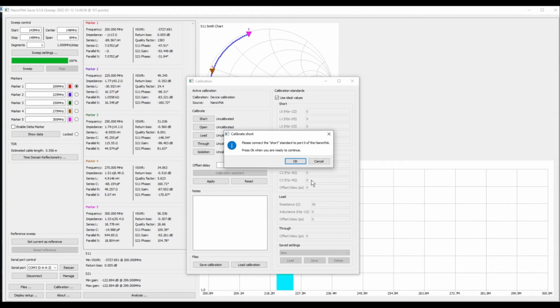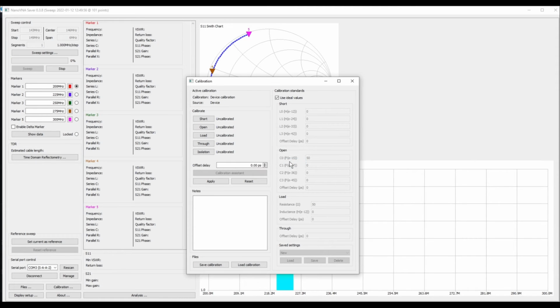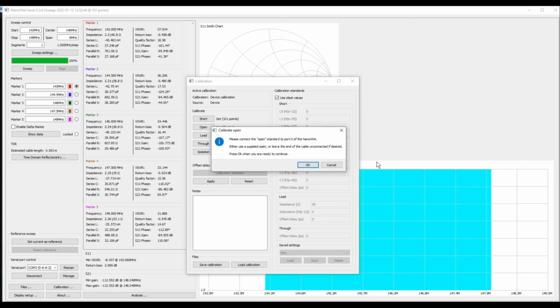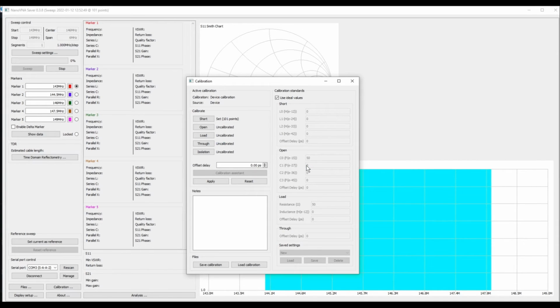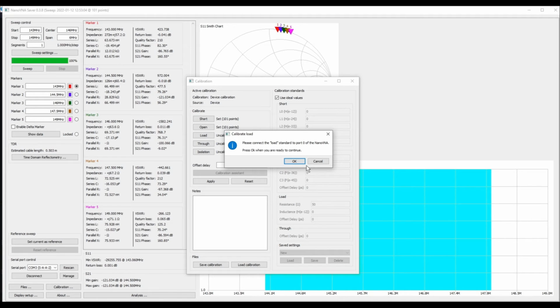It asks me to connect the short standard to port 0, and I can do that. So I'm going to do that right now, and then I'm going to click OK to continue. Now I'm not showing the connecting of these standards because I showed that earlier in the video. It's the exact same process. So I click OK, and it will do a sweep, and now it comes back and tells me to connect the open standard. So let me do that real quick. And then now I'm going to click OK. Now that that's done, it's asking me to connect the load standard. And that's easy enough. The load standard is connected, so I'm going to click OK.